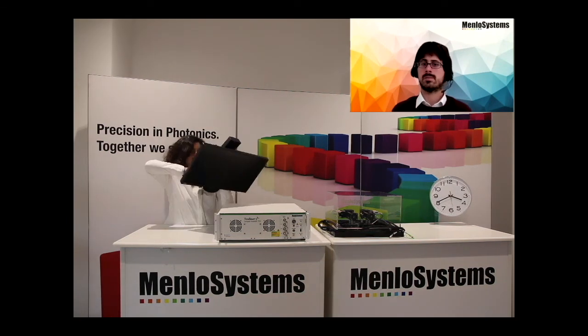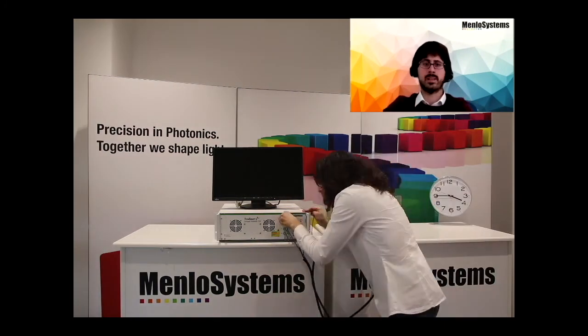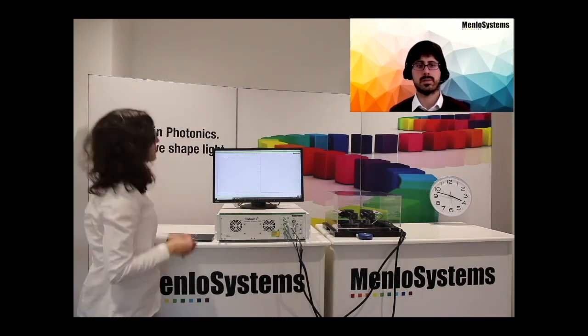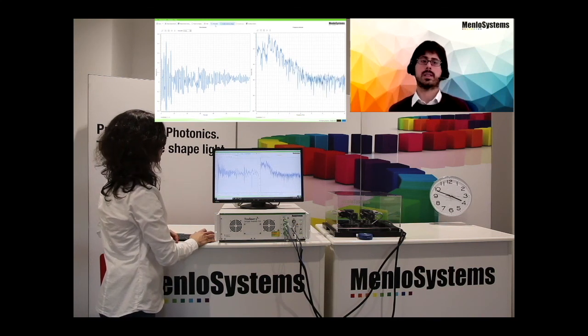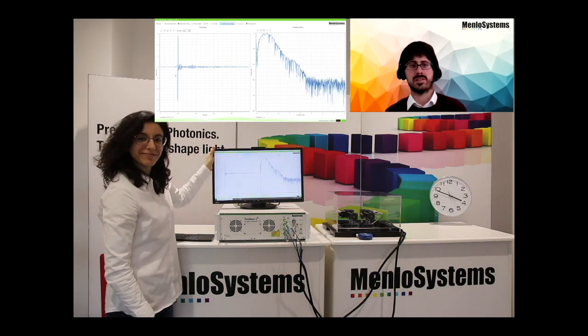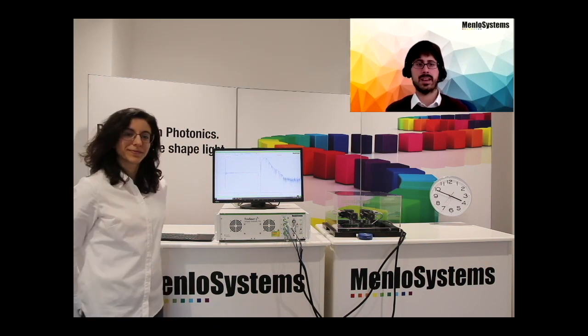If you don't see a pulse, you may start a search procedure as we defined. The instrument will center automatically to where the THz signal is located. And now we are seeing a THz pulse — congratulations! That's your first signal acquired with your new system. Now it's up to you — I hope you will have fun with your new THz spectrometer.